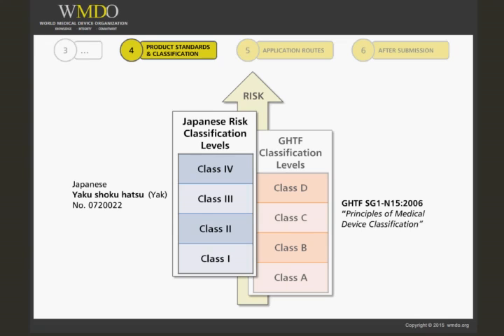Usually, you can use the GHTF guidance to classify your device, and the respective risk class is directly translatable to the Japanese class. For example, a class B device in the GHTF guidance will usually result in a class 2 device in Japan.